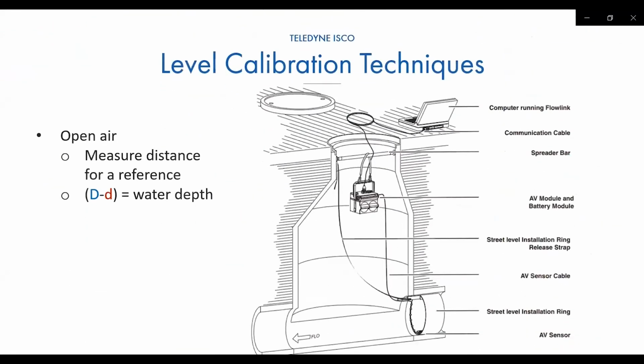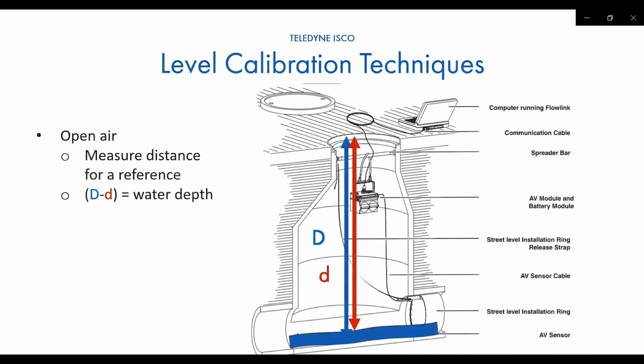Now on to other open air calibration techniques. What we're looking at here is an ISCO 2150 with an area velocity sensor. To avoid the confined space entry, when you're setting up the whole system, get the overall distance, from the top of the manhole all the way to the bottom of the channel. Say this is 10 feet. That would be our reference. Then take another measurement from that same point at the top of the manhole to the top of the water. If this is 9 feet, take my 10 feet overall distance minus the 9 feet. Now I know that my water depth is 1 foot.